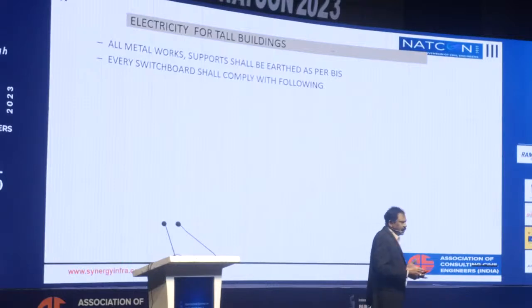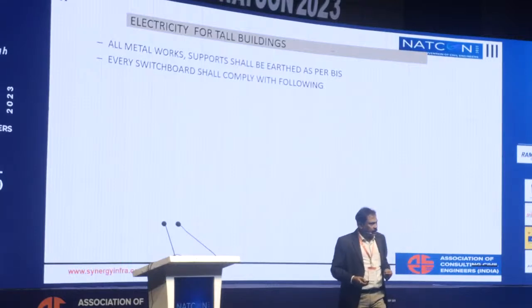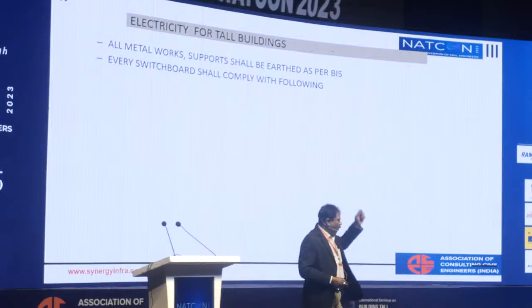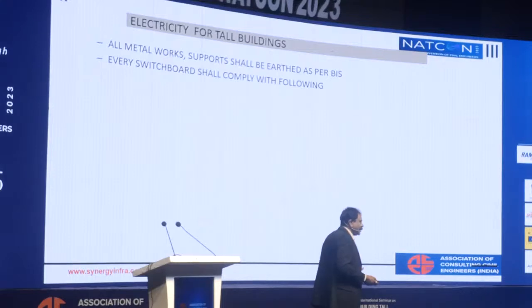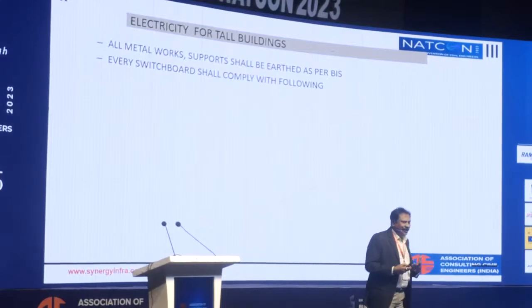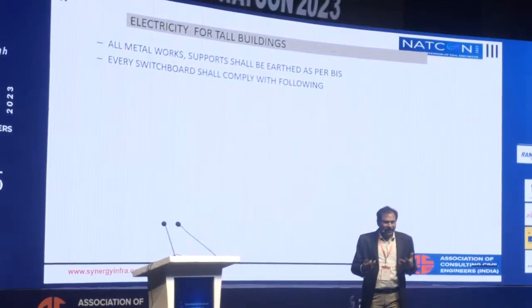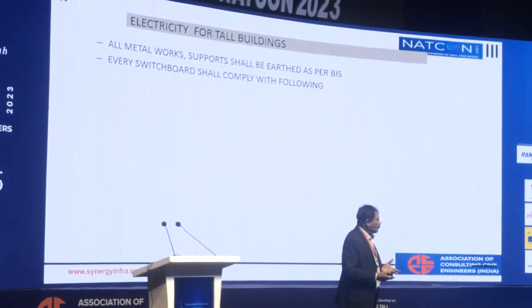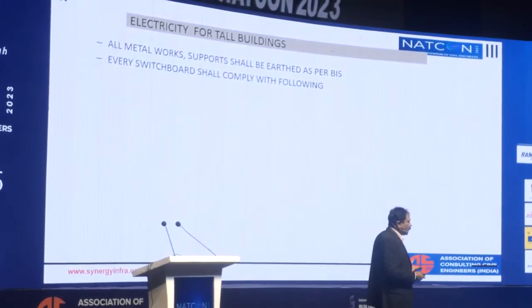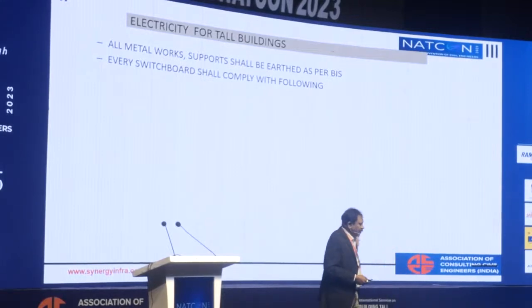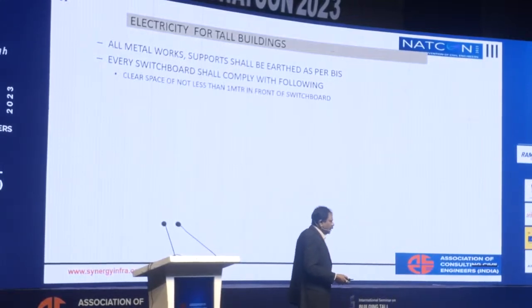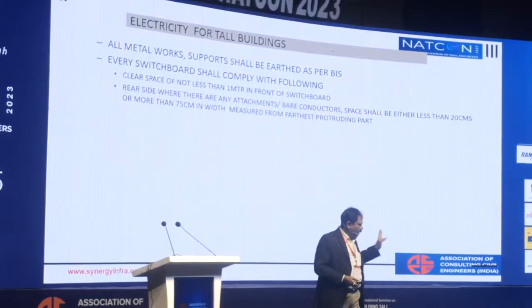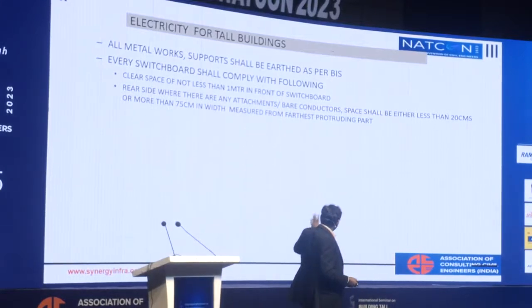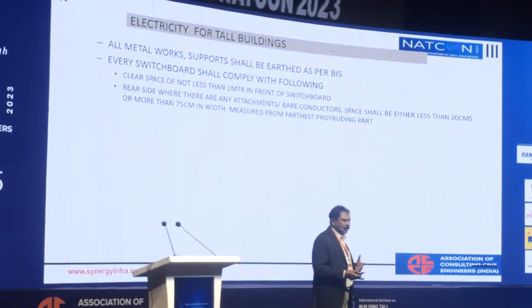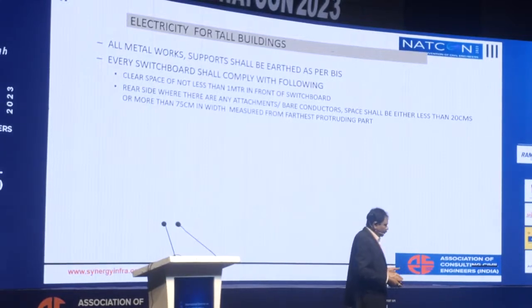The IEC 62305 for lightning protection says very clearly all the columns have to be used as down conductors. And I have come across some structural engineers saying that it is difficult for us, something may happen if there is a lightning attack, the structure may collapse, or something can happen if fault currents are taken through the structure. So that is the reason I would like to bring up some of these points, especially with photographs. And you see, these are some safety guidelines, like what should be the clearances between these panel boards or in front of the switchboards.